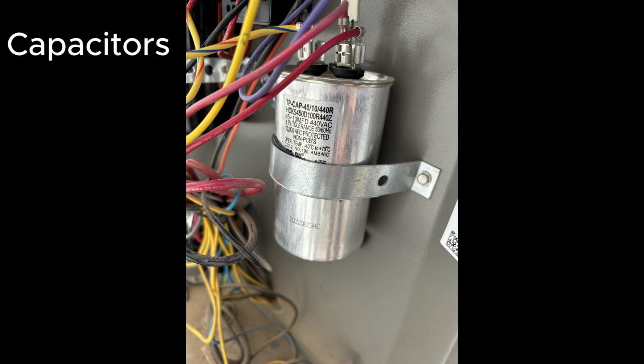Condenser fan motors at the condenser, or your blower motor, which we've talked about already, if they need a capacitor, the capacitor will make the motors not turn on. They are an extension of the motors. There's three motors. There's the blower motor, there's the condenser fan motor, and there's the compressor. So that's what capacitors are. They're batteries. They're very common on maintenances. We recommend changing them out if they are below about 10% of the rated value.